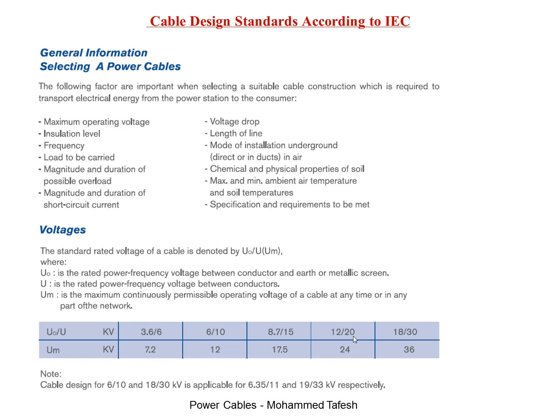If we are talking about a cable working on an applied voltage of 12/20, this means that 12 stands for the rated voltage between the phase and the ground — that is, the voltage between conductor and earth or between the conductor and the metallic screen — while 20 stands for the voltage between two conductors, two phases. U and UM represent the maximum voltage which the cable can bear.